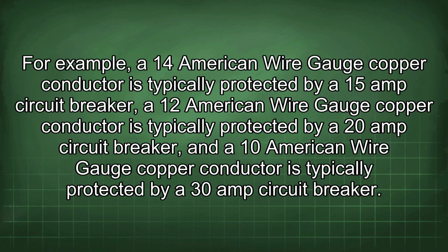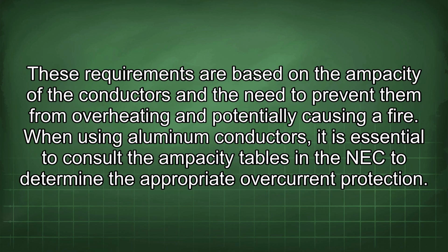For example, a 14 American wire gauge copper conductor is typically protected by a 15 amp circuit breaker, a 12 American wire gauge copper conductor is typically protected by a 20 amp circuit breaker, and a 10 American wire gauge copper conductor is typically protected by a 30 amp circuit breaker. These requirements are based on the ampacity of the conductors and the need to prevent them from overheating and potentially causing a fire.